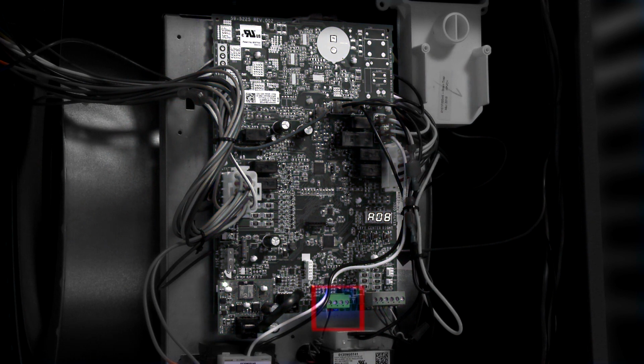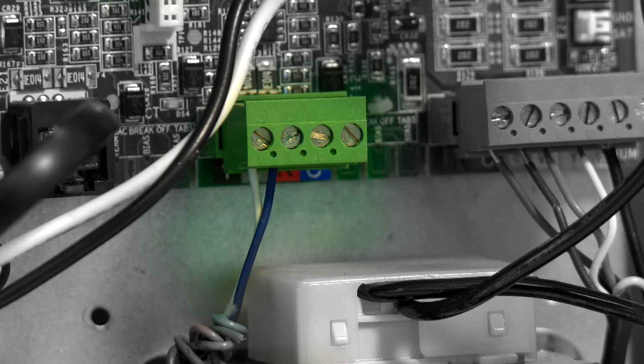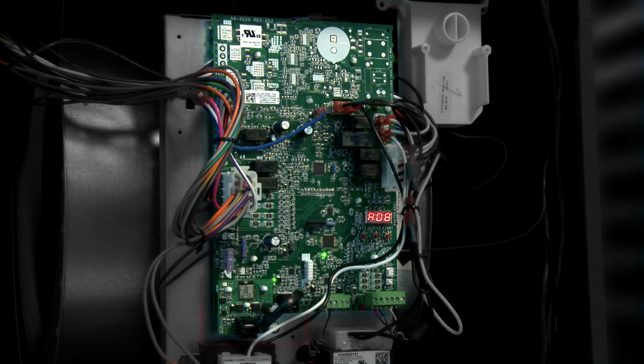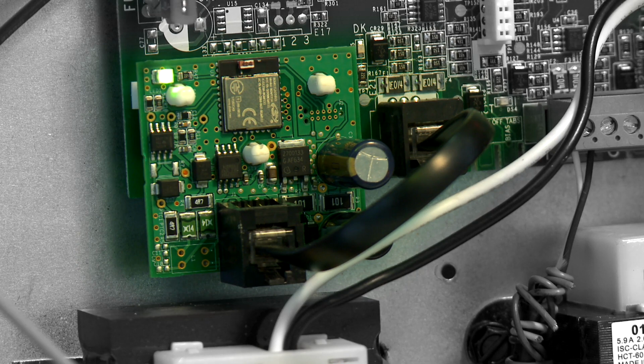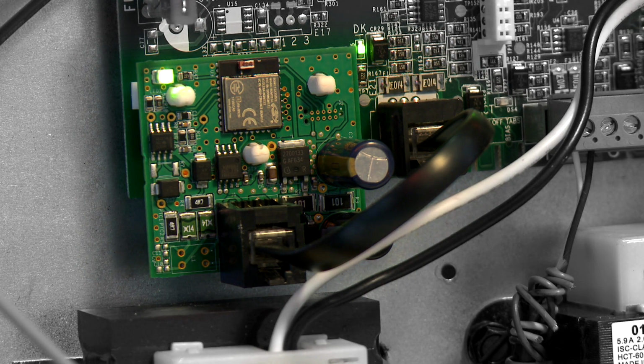To the left of the thermostat connection is the 2-wire connection to the outdoor communicating equipment. This can be either an air conditioner or a heat pump. Also, a single-stage heat pump or air conditioner can also be connected using the analog connections described previously. The small square board to the lower left is the Bluetooth connectivity board. It's an independent board with a connection from the main board via an RJ11 connection. This is the board that allows wireless connectivity from the HVAC system to the CoolCloud app. The flashing light on the Bluetooth module provides an indication that the Bluetooth module is operational.